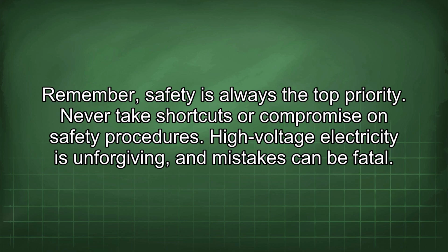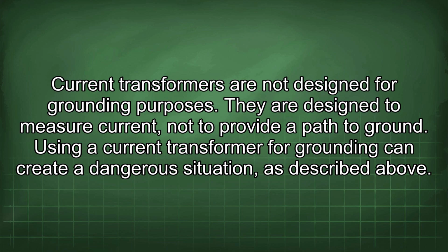Remember, safety is always the top priority. Never take shortcuts or compromise on safety procedures. High-voltage electricity is unforgiving, and mistakes can be fatal. Current transformers are not designed for grounding purposes. They are designed to measure current, not to provide a path to ground. Using a current transformer for grounding can create a dangerous situation, as described above.